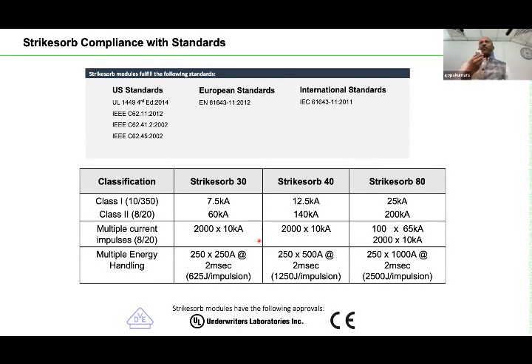If you look at the test procedure for a DIN rail mounted SPD, an impulse current is given. So a lightning current flows through the SPD, then it heats up. Then it has to be cooled down to room temperature, then the next impulse is given. Again, cool down, for 20 strikes, for example. Every time the current flows, it gets hot, is brought down to room temperature, and the next impulse is given. We should understand that lightning, after one flow, will not wait for the SPD to cool down. You got it? Lightning may be continuously coming. So that means there is a risk. Even if you have the best DIN rail mounted SPD, there is a risk that it may fail if the lightning is continuous.